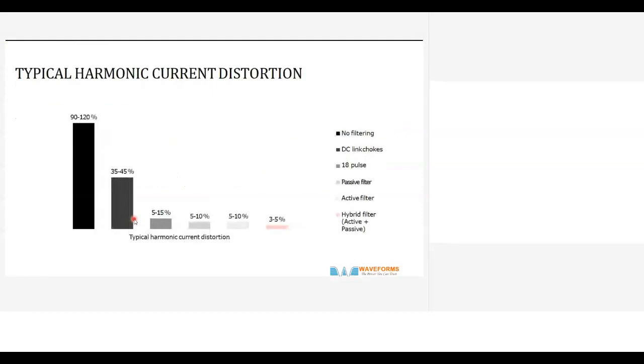Normally, in a drive, you can find up to 90 to 120% current distortion. With some drive chokes, it is only about 35 to 45%. Some use passive filters to reduce it to 15%. Some use hybrid filters, active and passive, and reduce it to a minimum of 3 to 5%. So different techniques are employed. There's always a cost involved: when you have to reduce further, the complexity increases.